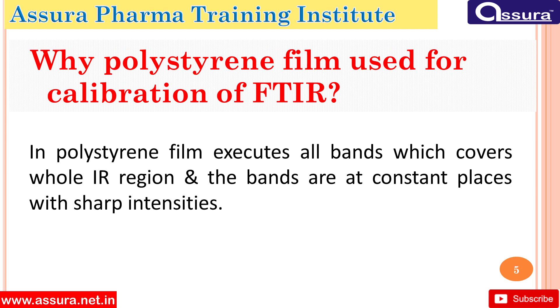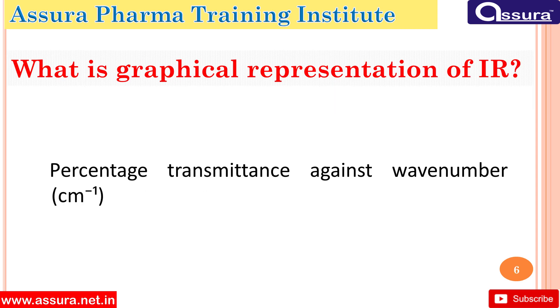Next, why is polystyrene film used for calibration of FTIR? Polystyrene film exhibits all bands which cover the whole IR region, and these bands are at constant positions with sharp intensities. Next, what is the graphical representation of IR? The graphical representation of IR is percentage transmittance plotted against wavenumber.